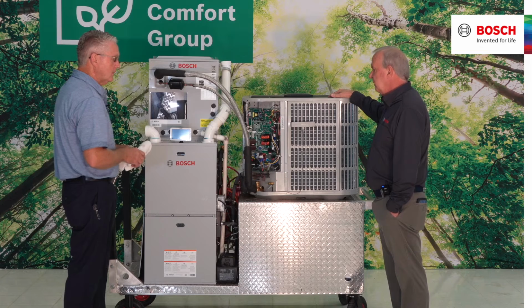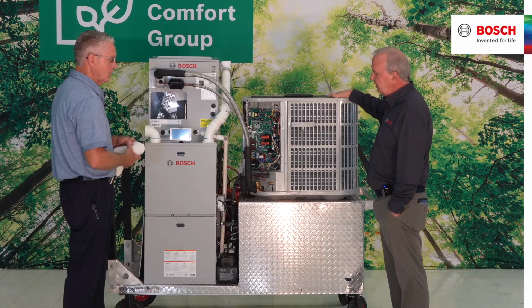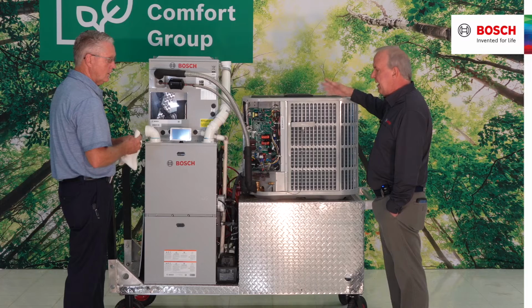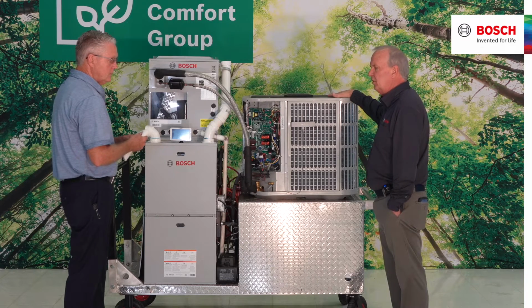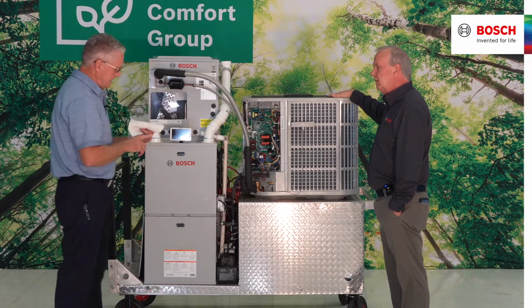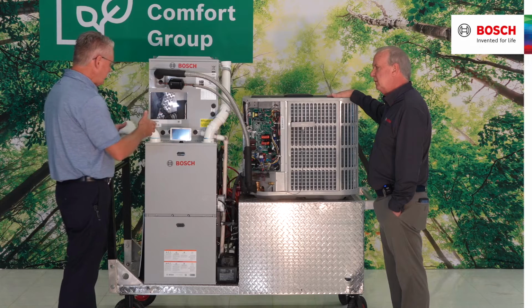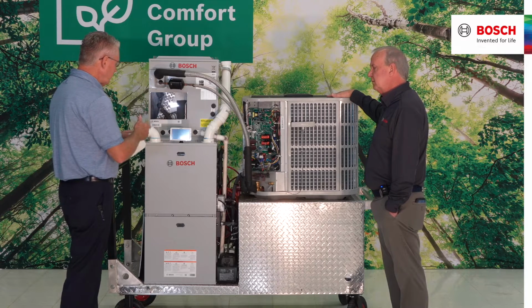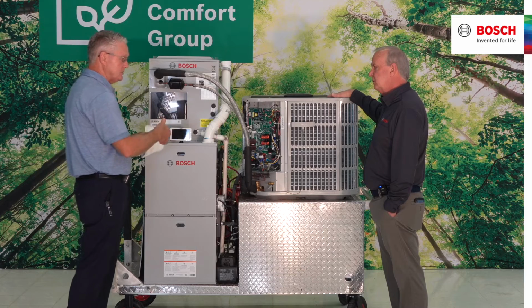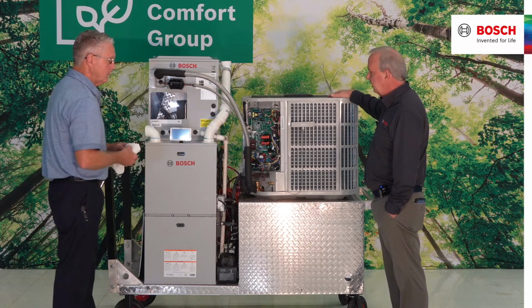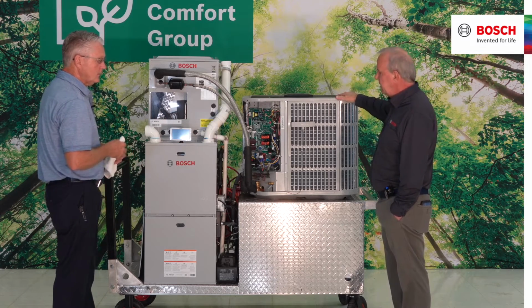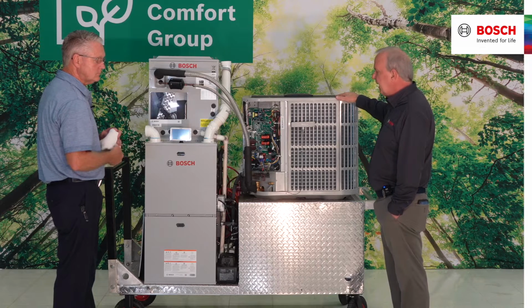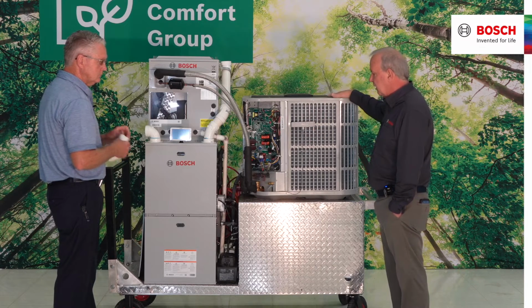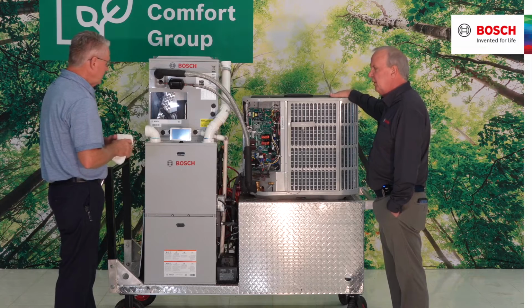Okay, and you mentioned the 4 different BTUs, like a high, medium, and low. What are we talking about? So yeah, we're talking about literally a 60,000, an 80,000, and then a 100,000, and then a 120,000 BTU output. Okay, good.